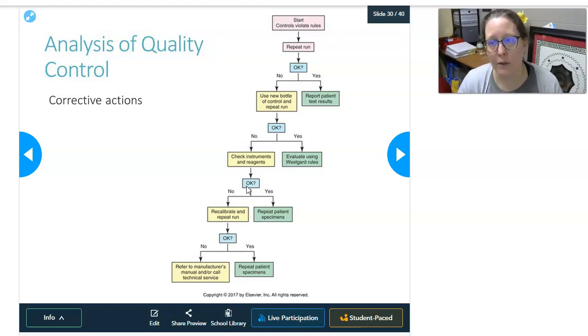So that means we've run QC like 4 or 5 times by now, right? And if that works, then you can repeat your patient specimens that you had run and start turning out patient results. So that means that your quality control came in after you recalibrated. And if that still didn't work, then that's when you call tech support, that you're at the limit of what you can do.